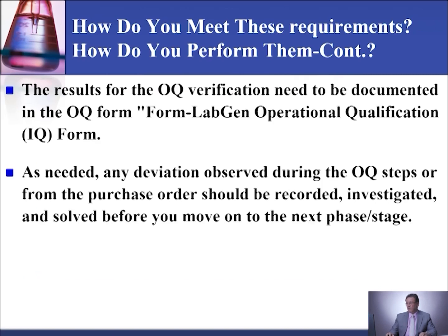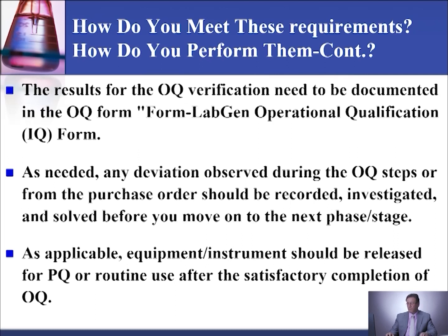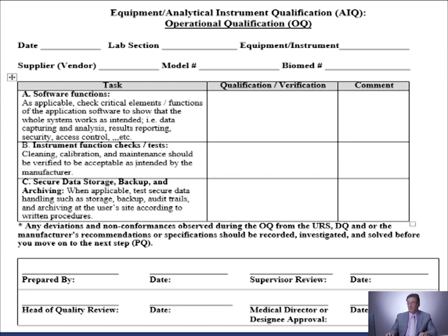The results for the OQ verification need to be documented in the OQ form called LabGen Operational Qualification Form. As needed, any deviation observed during the OQ step or from the purchase order should be recorded, investigated, and solved before you move on to the next stage. As applicable, equipment and instruments should be released for PQ performance qualification or routine use after the satisfactory completion of the OQ. This is the form that you could use for the operational qualification.